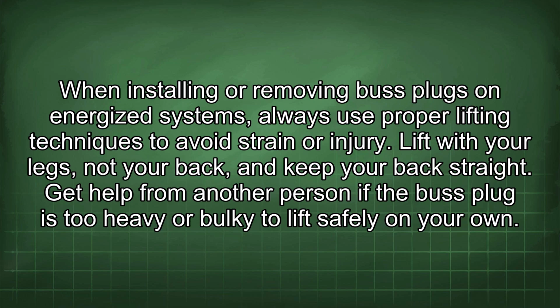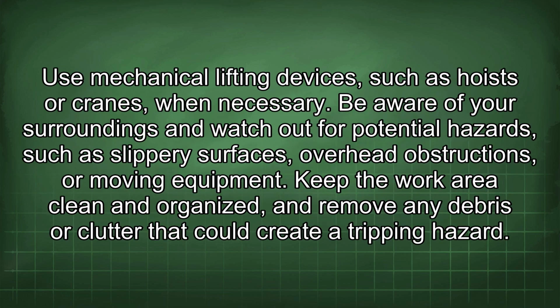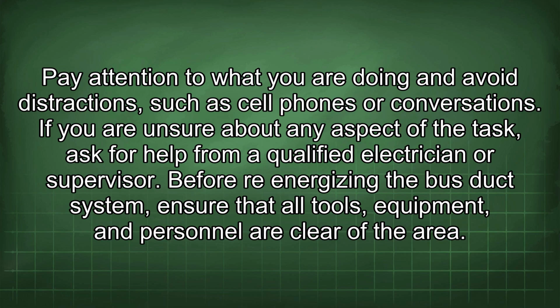Lift with your legs, not your back, and keep your back straight. Get help from another person if the bus plug is too heavy or bulky to lift safely on your own. Use mechanical lifting devices, such as hoists or cranes, when necessary. Be aware of your surroundings and watch out for potential hazards, such as slippery surfaces, overhead obstructions, or moving equipment. Keep the work area clean and organized, and remove any debris or clutter that could create a tripping hazard. Pay attention to what you are doing and avoid distractions, such as cell phones or conversations. If you are unsure about any aspect of the task, ask for help from a qualified electrician or supervisor.